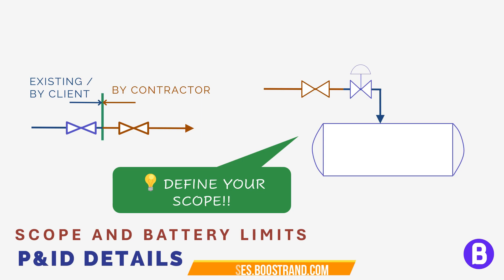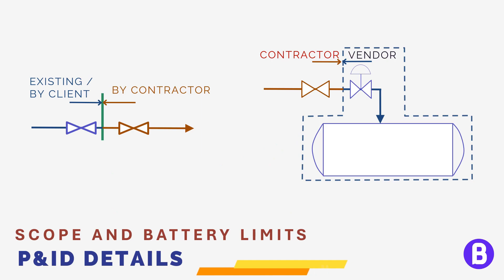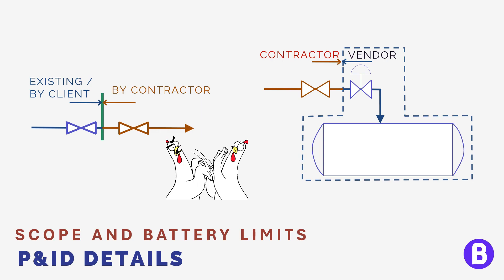We are expected to define what we want the package vendor to provide and what we shall purchase ourselves. We shall draw a dashed box — what's inside this box, shown in blue, shall be provided by the vendor, and we shall provide the valve and interconnecting piping in red, which is outside the box. If these are not defined well, many conflicts may occur between different parties, and people shall start to throw responsibilities on each other, leading to many issues during project execution.